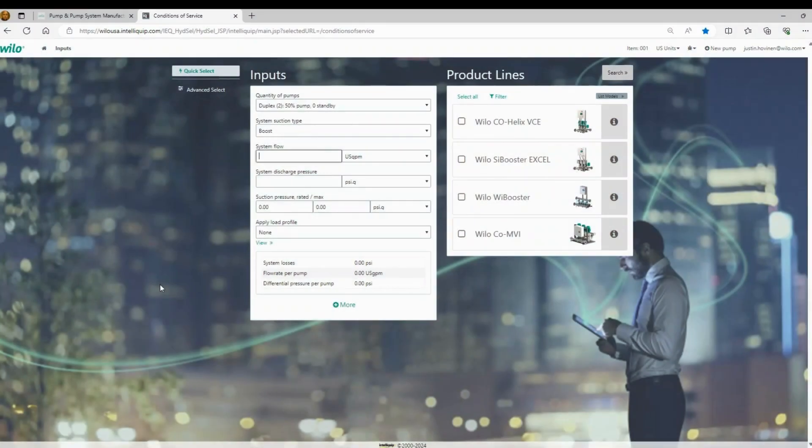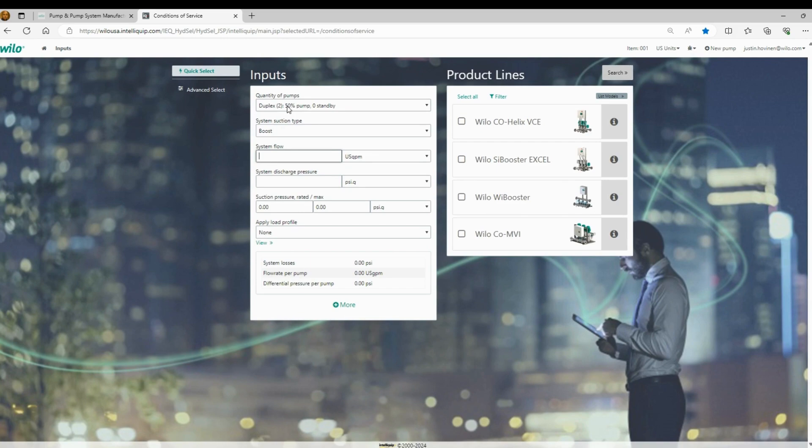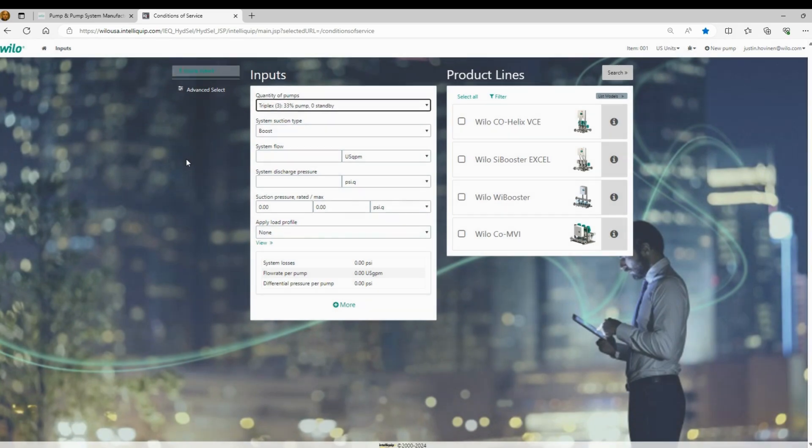We'll click on the multi-pump system. This is what our quick select home screen looks like. You can see in the center, we have inputs, and then on the right side, we have the product lines to choose from. We'll start out at the top. There's options for quantity of pumps and then how those pumps are split for flow. On the duplex, you can do 50% per pump, so both pumps are needed to hit primary duty. Or you can do one pump at 100% of duty with one standby. And it's the same thing for triplex. You can choose 33%, so three pumps are required to hit duty, or you can have two pumps required for the duty, so each can handle 50% with one standby.